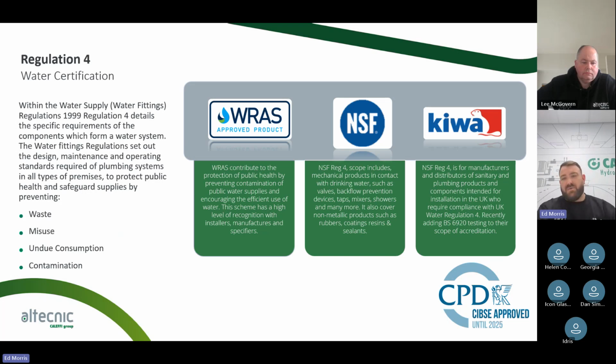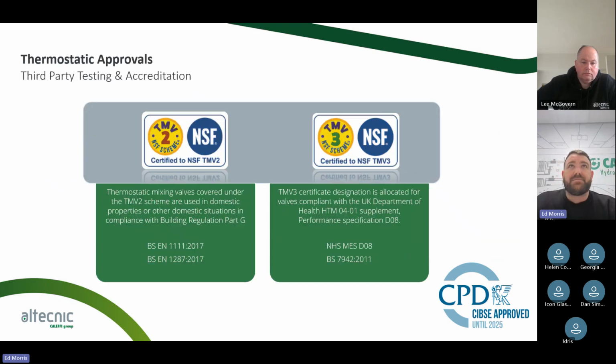We always traditionally look at Regulation 4 as WRAS, but there are other ways that you can now show compliance to Reg 4. So you've got the WRAS approval, you've got an NSF Reg 4 approval, and you've also got Kiwa Reg 4. So as I said before, traditionally people always direct straight to WRAS, but all WRAS does is show compliance to Reg 4, of which now other standards will approve to the same as well. So a bit about regulation. We'll talk about WRAS approval certification. It's all about compliance to that Regulation 4 of the Water Act.